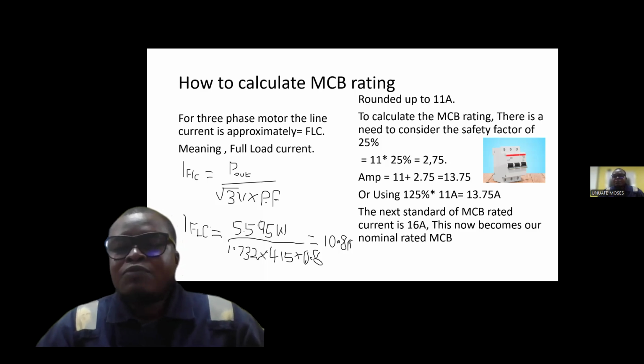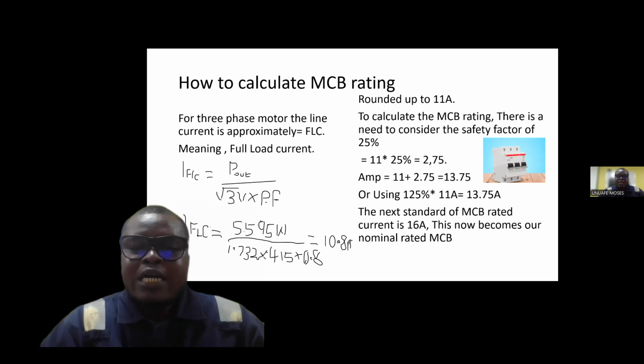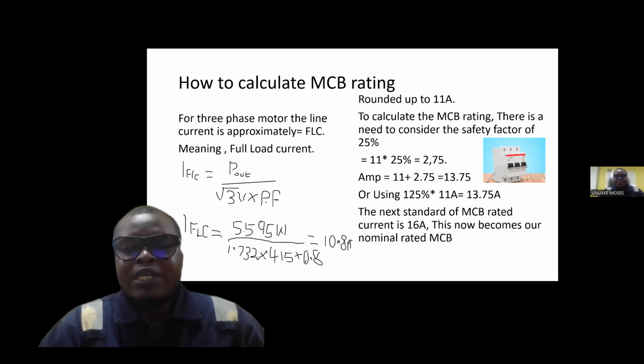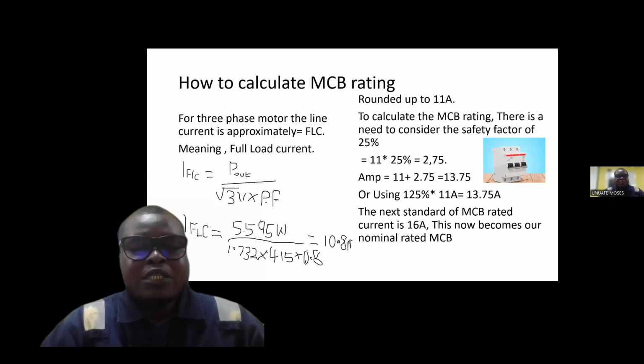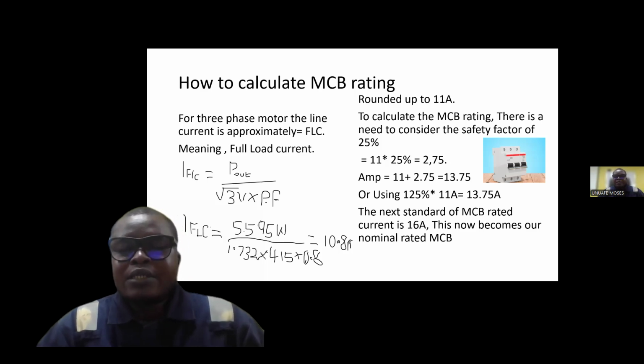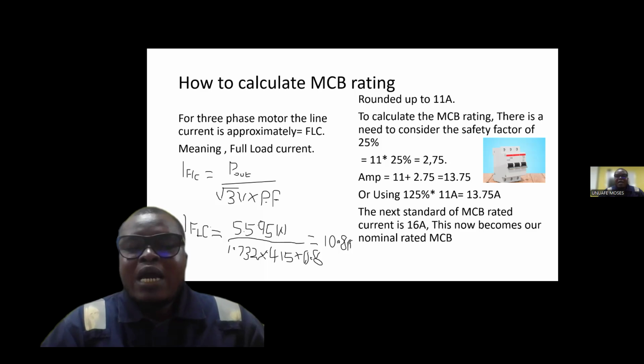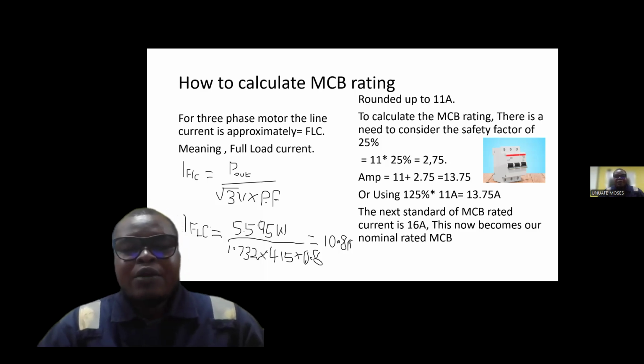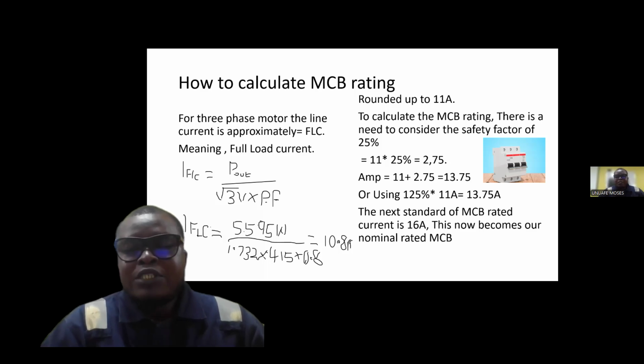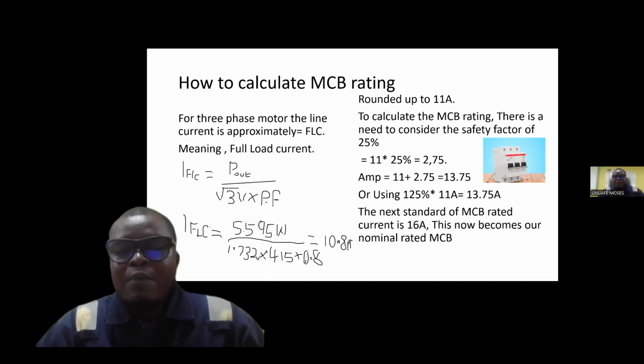there is a need for us to consider the safety factor. And the safety factor is going to be 25% as the standard. So when you use 25% to multiply your FLC, which is your full load current, it is going to give you 2.75. And now 2.75 added to the FLC, your full load current, is going to give you what? 13.75 amps.